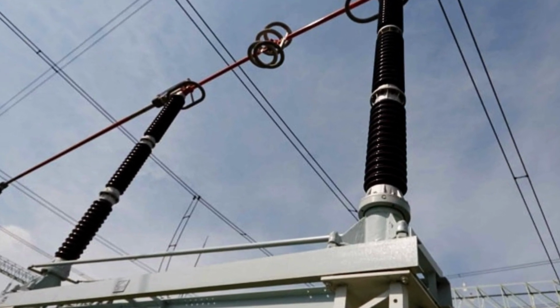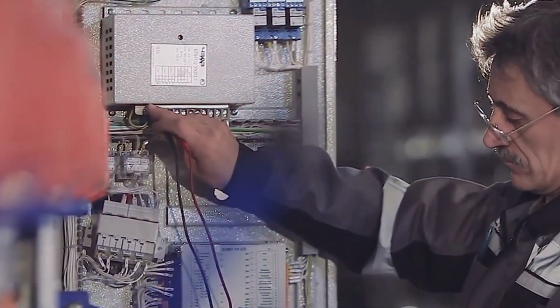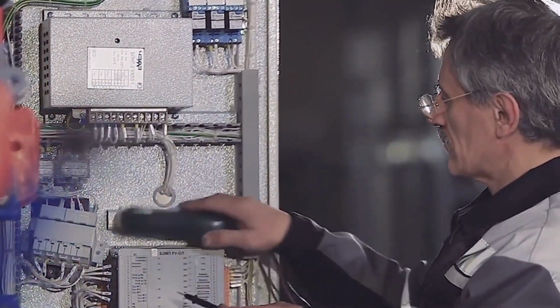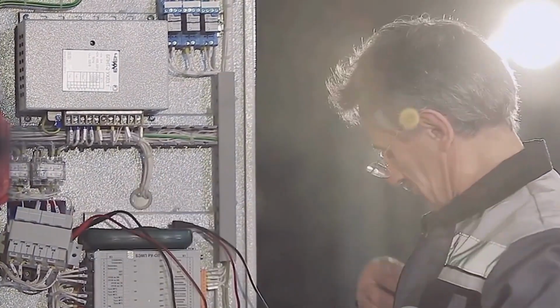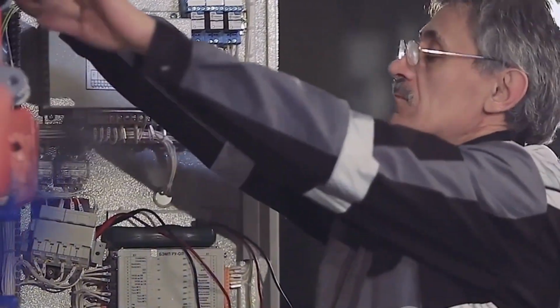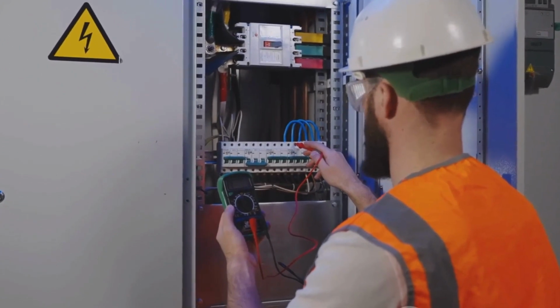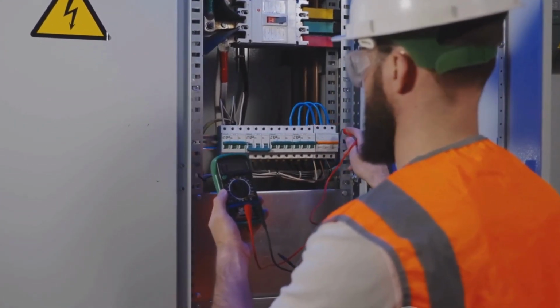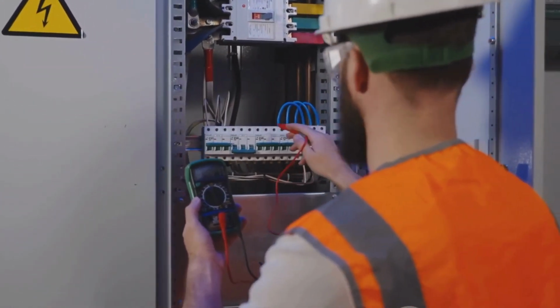On the flip side, we have isolators, or disconnect switches, as they are sometimes called. These are designed to physically disconnect a part of the electrical system for maintenance or repair purposes. They're not built to interrupt the current under normal operating conditions, unlike circuit breakers. So, while they may seem similar, these two components have very different roles in a power system.